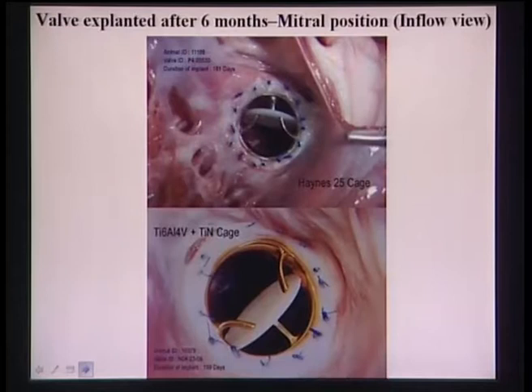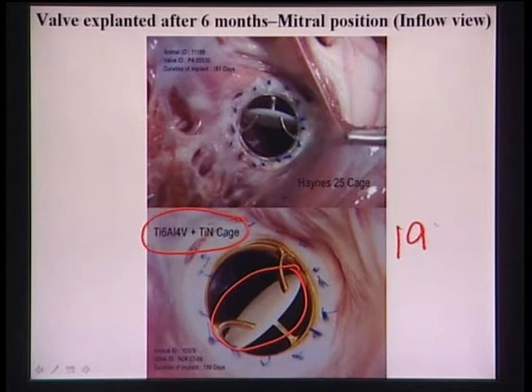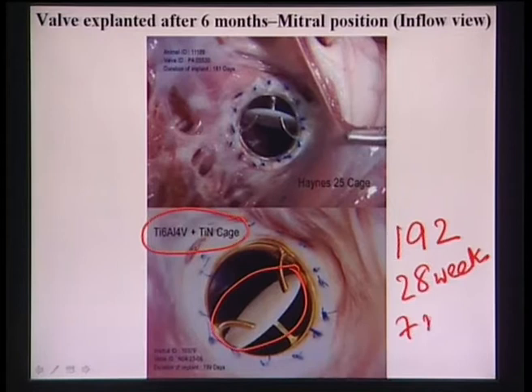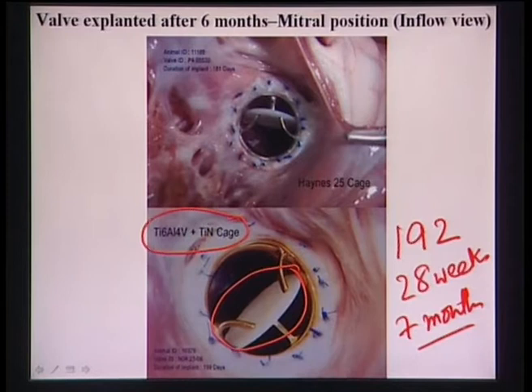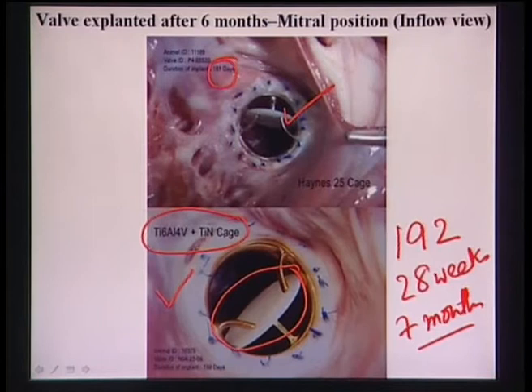An example of an artificial heart valve made of Ti-6Al-4V plus titanium nitride coating was implanted in animals. After 192 days - approximately 28 weeks or 7 months - comparing with and without titanium nitride coating, the coated material shows much better performance. This concludes the discussion of in vitro and in vivo hemocompatibility for blood-contacting devices.